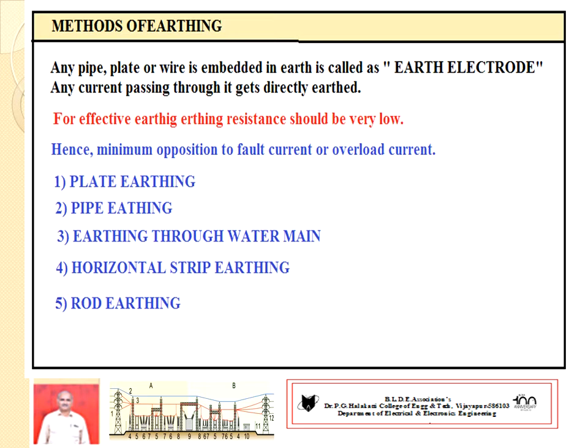It may be a plate, a pipe, a water main, or a horizontal conductor, or a rod. Depending upon the type of electrode, the name is abbreviated to the respective earthing. If we are using a plate as the earth electrode, then it is referred to as plate earthing. If the earth electrode is a pipe structure, then it is referred to as pipe type earthing. If it is a rod, rod type earthing. The respective name should be given. You understand which type of electrode you are using. Rod earthing means we are using a rod as the earth electrode.